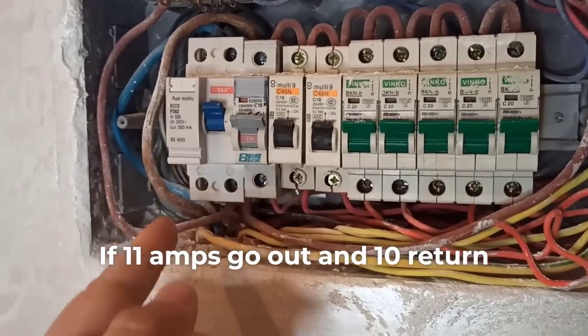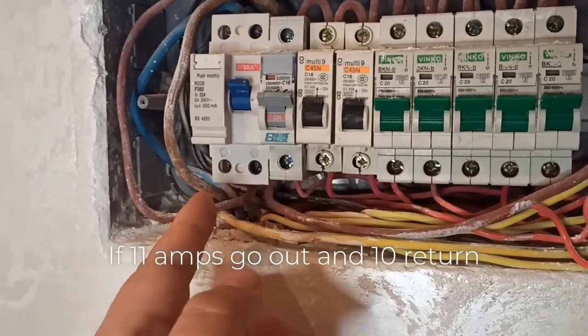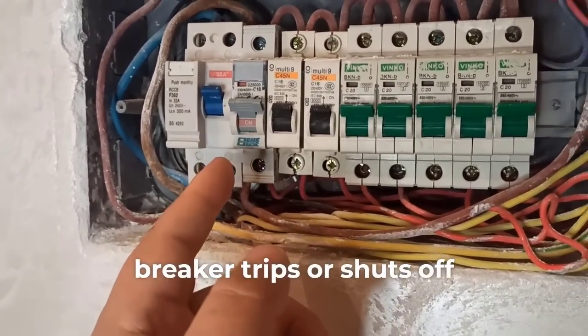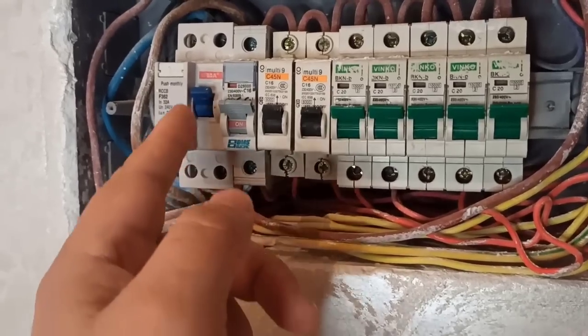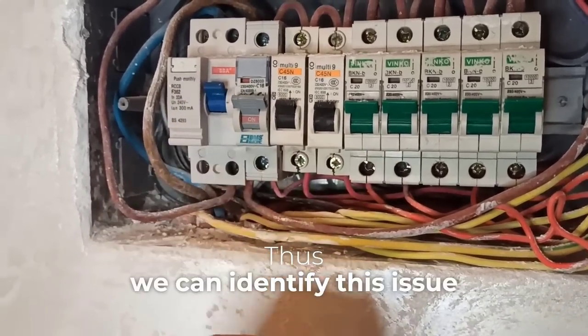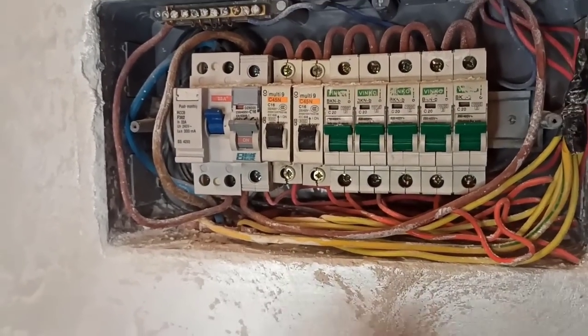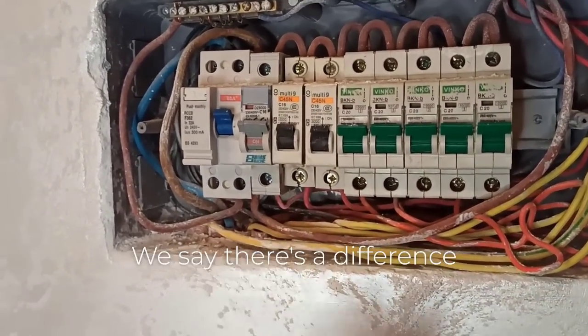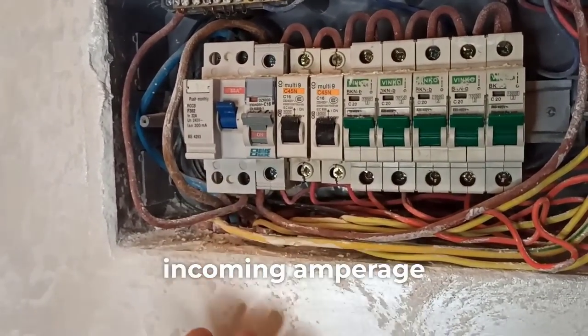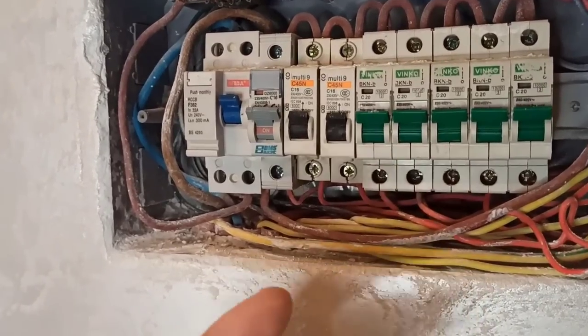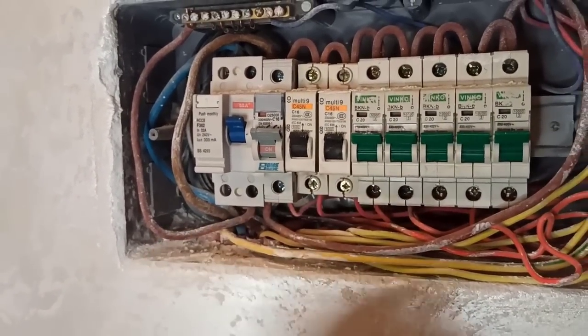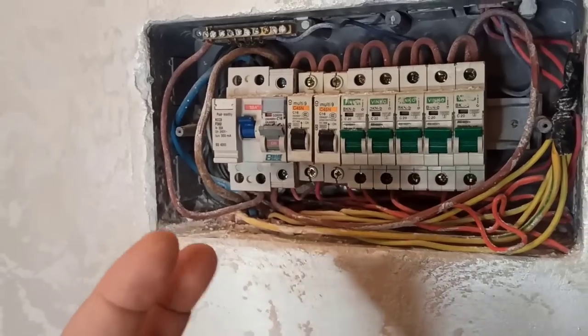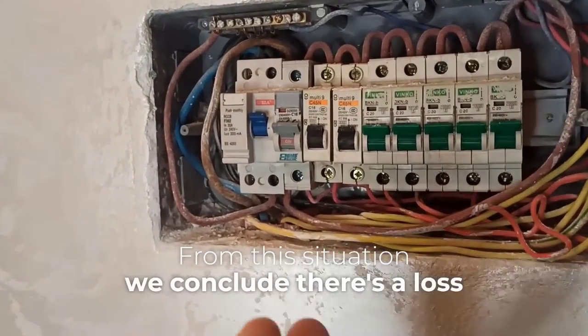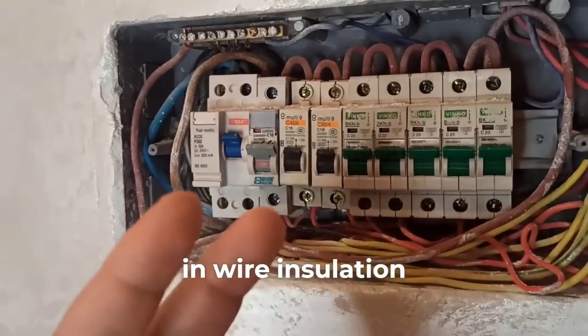If 11 amps go out and 10 return, the differential circuit breaker trips or shuts off. Thus, we can identify this issue. We say there's a difference between the outgoing and incoming amperage. From this situation, we conclude there's a loss in wire insulation.